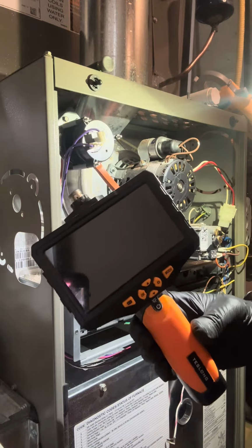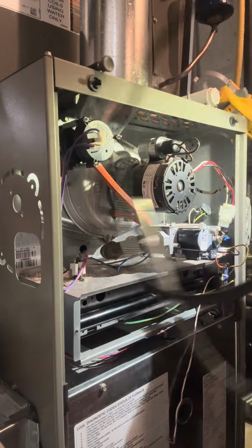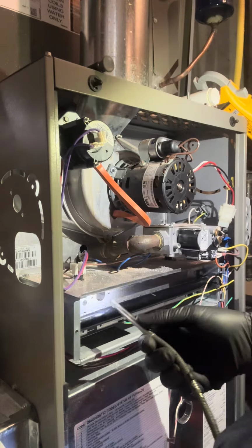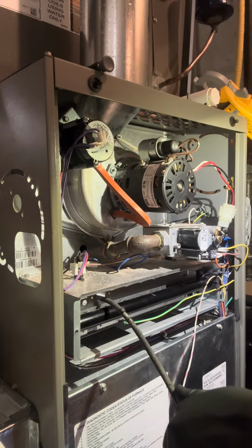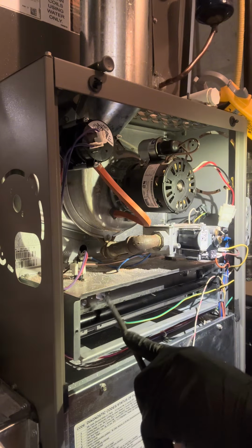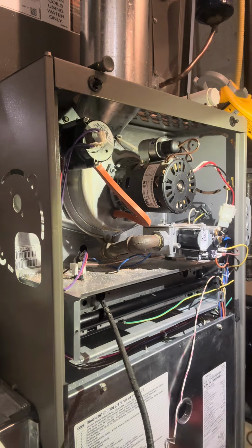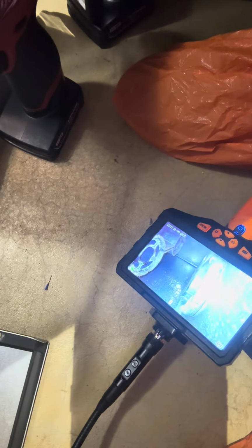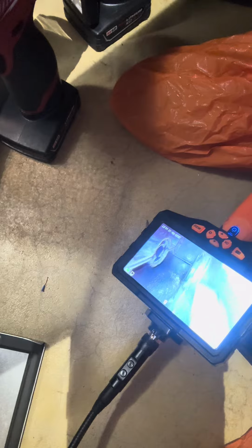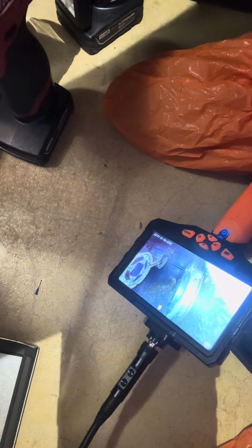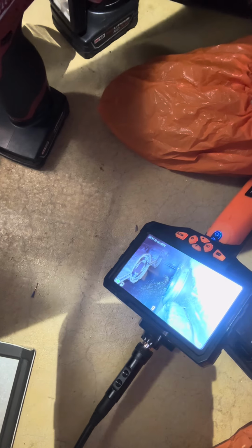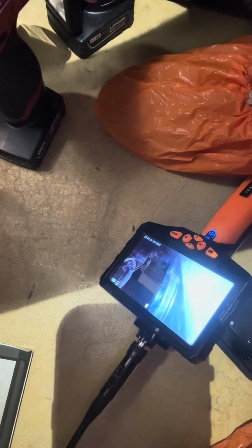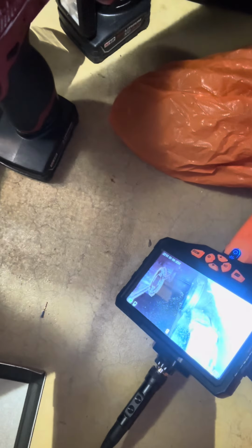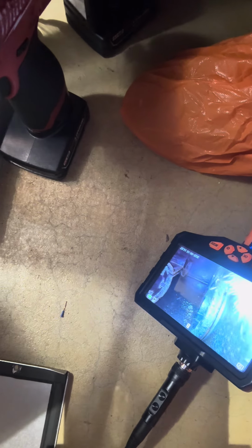Here's my handy dandy inspection camera, and here's my tube that goes along with it. Sticking this in there. And that's what I'm looking at there. These are your burners. These are where the flames shoot across and into your heat exchanger. So I am inspecting these burners for any massive amounts of corrosion, spider webs, or anything that looks unsafe.